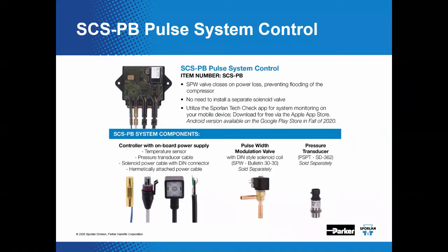Okay, the other flavor of this controller is the SCS-PB. Now, this is a controller that supports our pulse width line of valves. As seen on this slide, applying this controller to a retrofit application is very simple, and it's based on the variety of the valves that we have to offer, and all the different transducer types that Sporlan has to offer are supported. Again, to simplify this install, the temperature sensor, the transducer cable, the valve cable, and the power cable all come as part of this package.